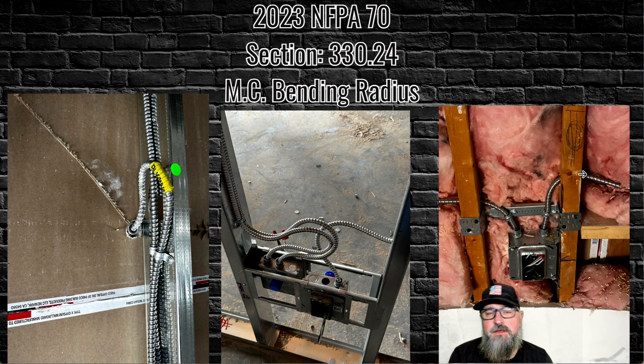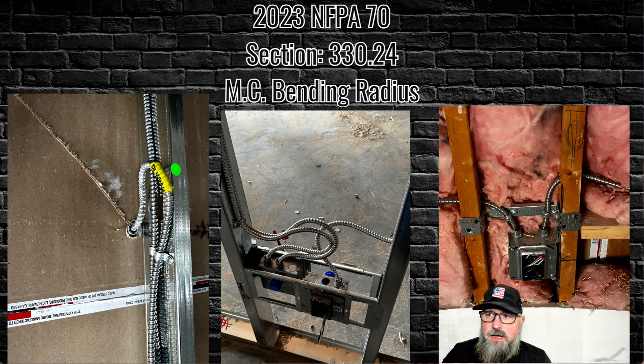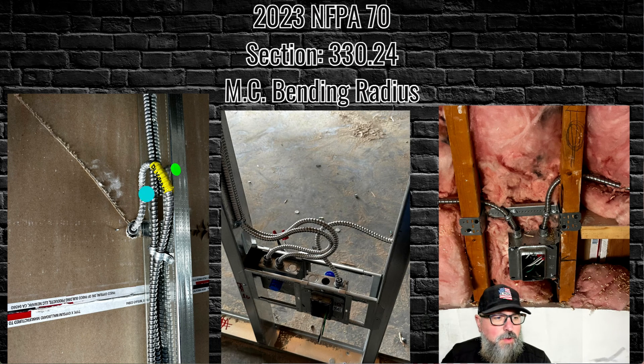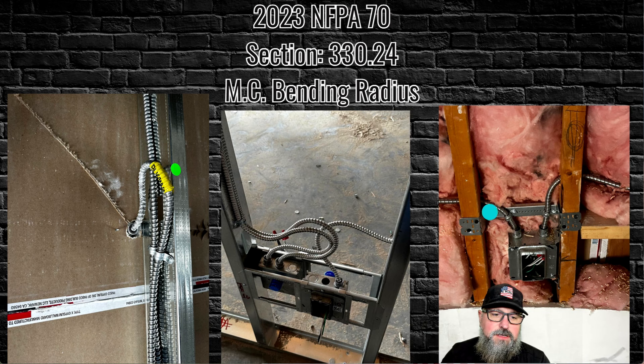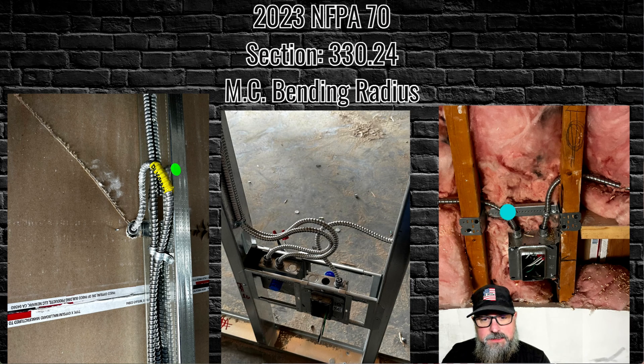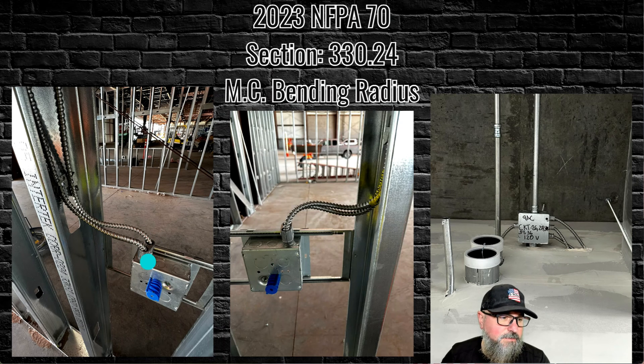Now here are examples of what I see in the field — MCs bent beyond the minimum radius. This one right here is way over-bent and will cause damage; it needs to be corrected. Same here — that doesn't look like seven inches; there's a lot of strain on that MC. What I see most often is when guys put MC into boxes through the tombstone knockouts in the wall studs — that puts way too much strain on the MC and doesn't achieve the proper bending radius. Again, too much strain out of the connector — over the bending radius.